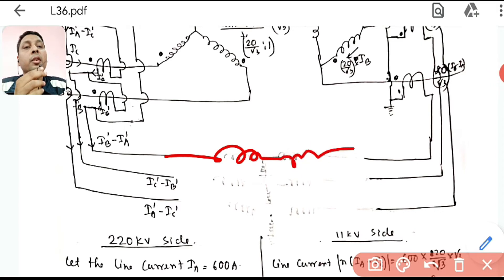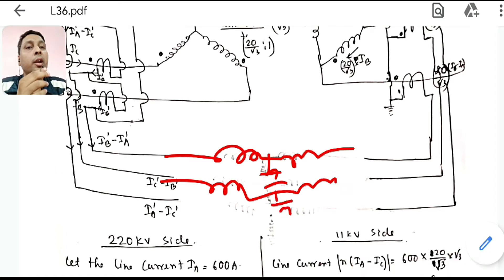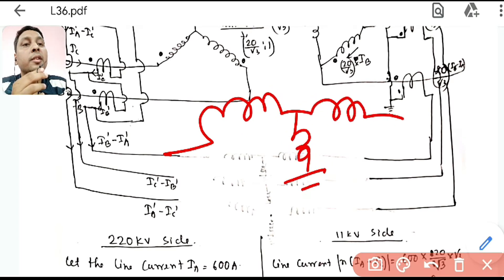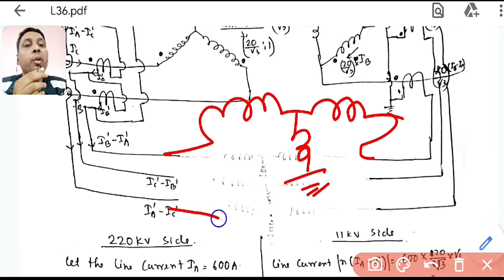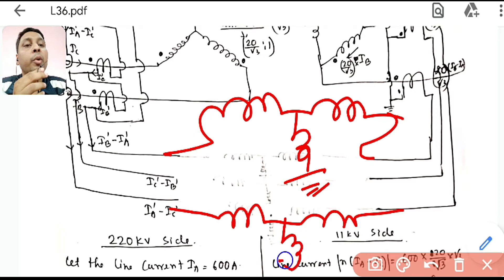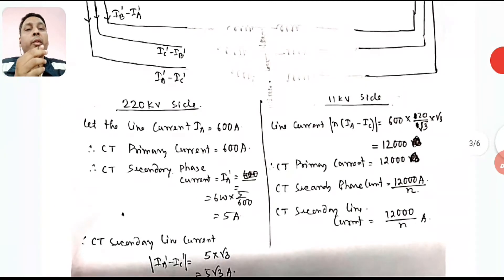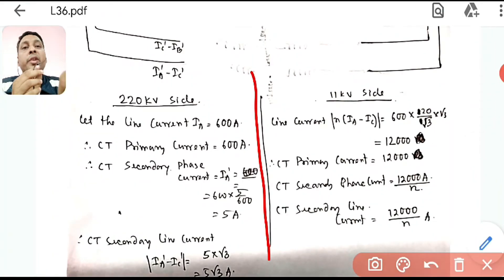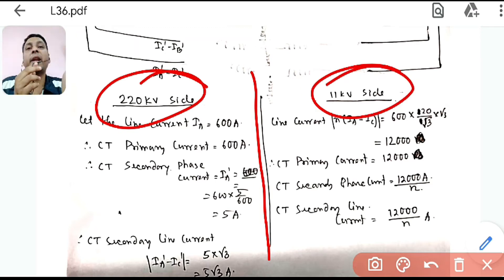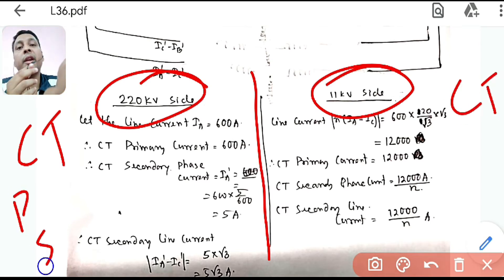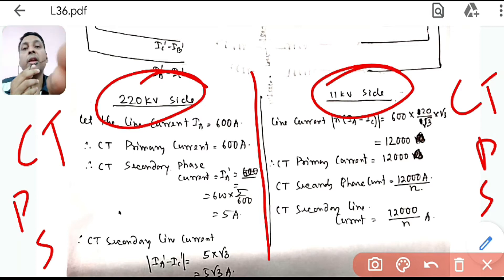This forms the standard percentage bias differential protection scheme. There are restraining coils and operating coils — the three phases are connected but without interlinking between them. The 220 kV side CTs and the 11 kV side CTs each have their own primary and secondary windings contributing to the relay.